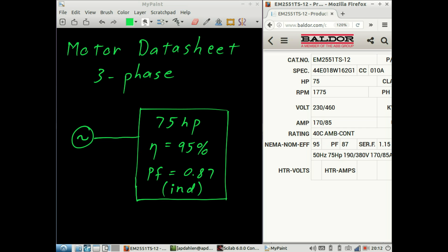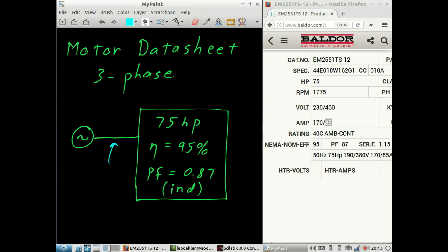It's a 75 horsepower machine. It has an efficiency of 0.95, a power factor of 0.87, and it operates on a 460 or a 230 volt system. We're going to look at the 460 volt system only. If we've done our job right, we should find that the line current is 85 amps when the motor is powered by a 460 volt AC system.